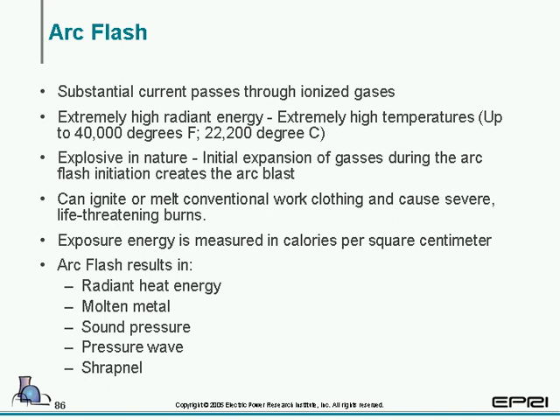It's explosive in nature. When you have an arc flash, the initial expansion of the gases during the flash initiation creates a blast, an actual explosion. This can ignite or melt conventional work clothing and cause severe or life-threatening burns. The exposure energy is measured in calories per square centimeter. After an arc flash safety analysis is performed, that's usually the end result. An arc flash results in radiant heat energy, molten metal, sound pressure, in other words, a blast and a pressure wave, and shrapnel.